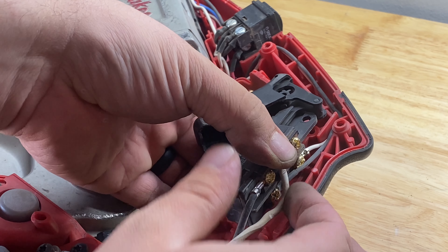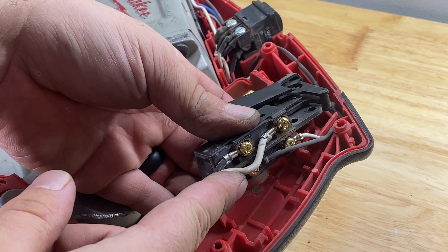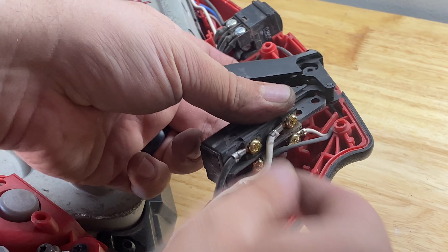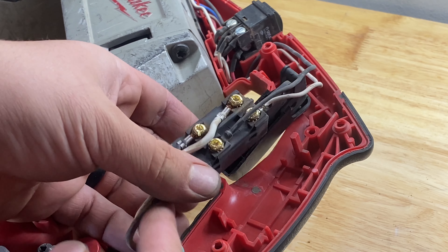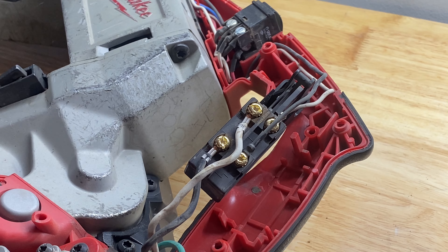On this model it's very straightforward — it looks like we just have to unscrew these connections and then put them on our new switch. I want to make sure they look the same, and they should fit just fine. Feel free to take a picture of the wiring — I'm going to go one wire at a time so it's hard to screw up.